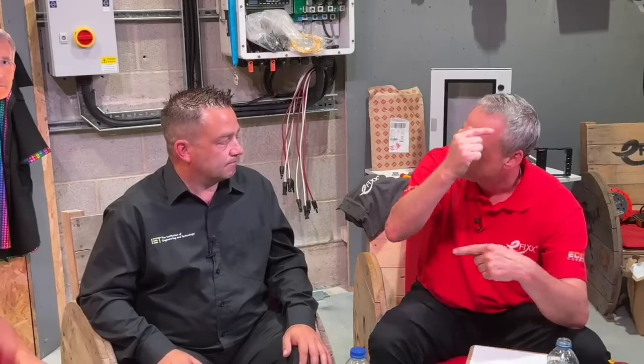Yep. But there could be, even if it's a momentary lapse in time, that circuit not disconnected, and therefore ADS might not apply and disconnect in the required time, or energise the circuit for a split second longer than needed? Yes, and people might say, but a PV inverter has to trip out in 0.5 seconds, which is correct to the new G98, but some of the older inverters, the maximum disconnection time was 2.5 seconds. So 0.4 has gone out the window? Yes, basically. And again, it goes back to it. Maybe that consumer unit's life has lapsed, hasn't it?